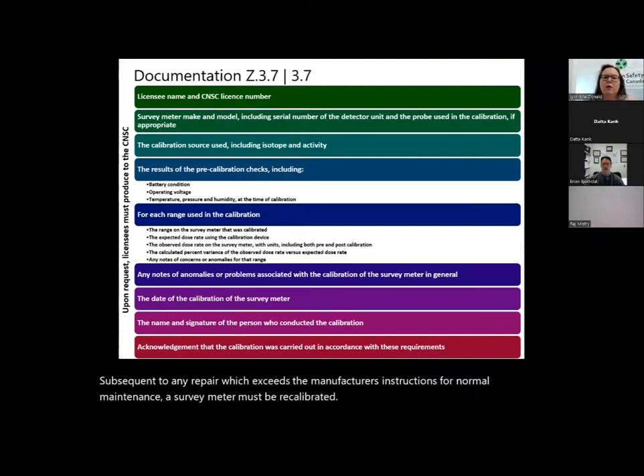In order to meet the requirements of Section 20 of the Nuclear Substances and Radiation Devices Regulations, licensees must make available on request to the CNSC a document for each survey meter which includes the following information: licensee name and CNSC licence number, survey meter make and model, including serial number of the detector unit and the probe used in the calibration, if appropriate, the calibration source used, including isotope and activity, the results of the pre-calibration checks, including battery condition, operating voltage, temperature, pressure, and humidity at the time of calibration.